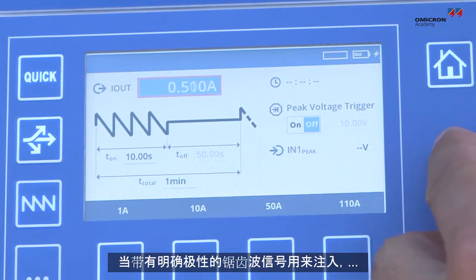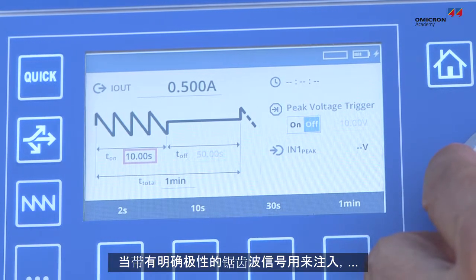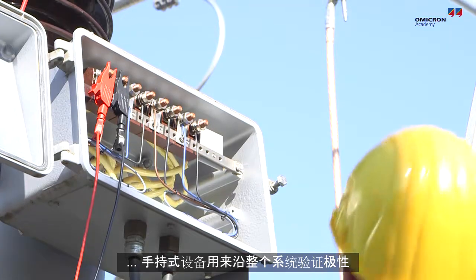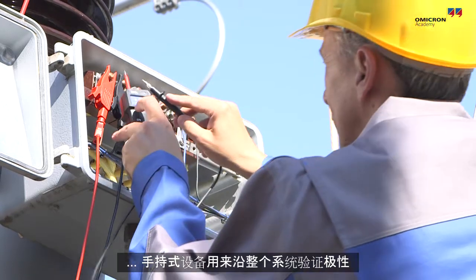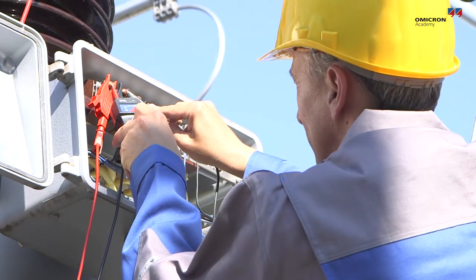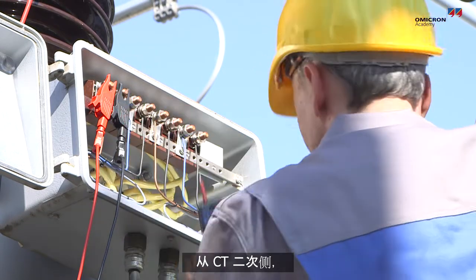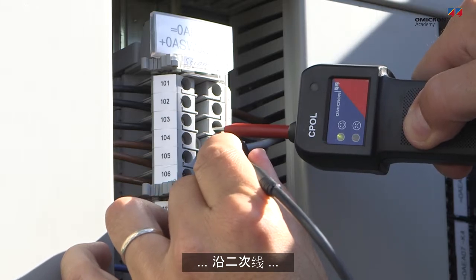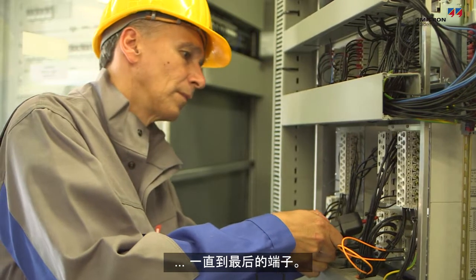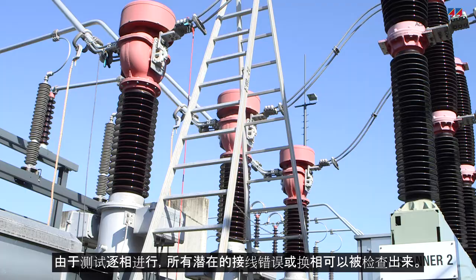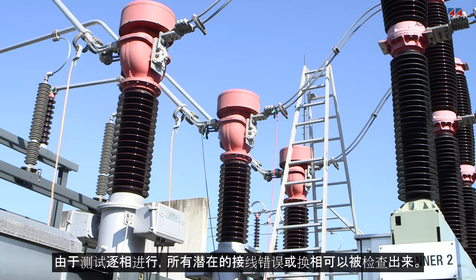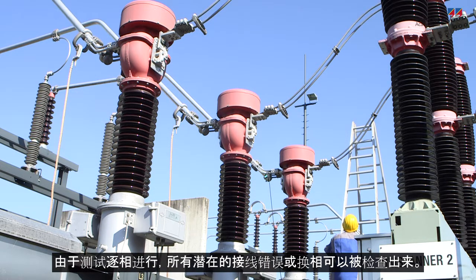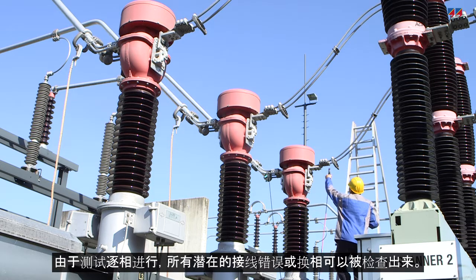When a sawtooth signal with a distinct polarity is being used for injection, a handheld device can be used to validate the polarity throughout the system, from the secondary side of the CT, along the secondary wiring, all the way to the last terminal. Since this test is done phase by phase, all of the potential wiring errors or phase swaps can be detected.